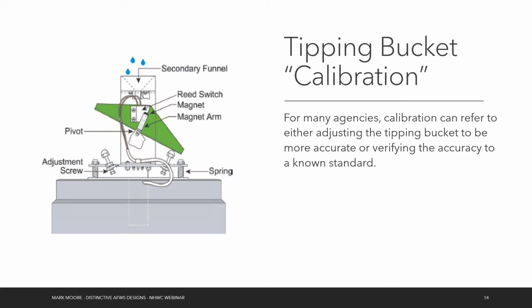So if you haven't seen one of these diagrams before, this is showing you how a tipping bucket works. You've got a funnel that brings in the water. Usually there's a much bigger funnel with screens over this. And you've got a bucket that can go back and forth. And as it pivots, this little magnet and magnet arm move past our reed switch, and that generates a signal that's picked up by a tipping bucket data logger. So it's just really counting 1, 2, 3, 4 every time it tips.